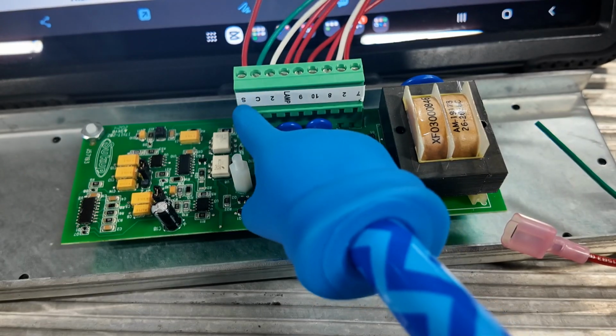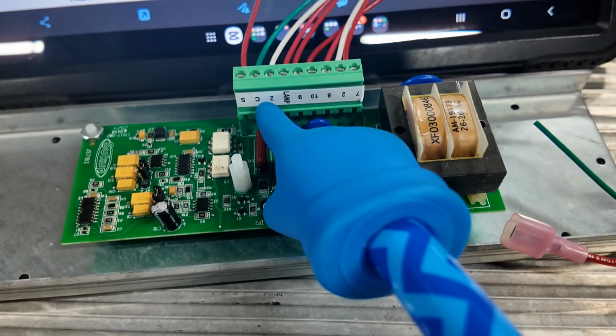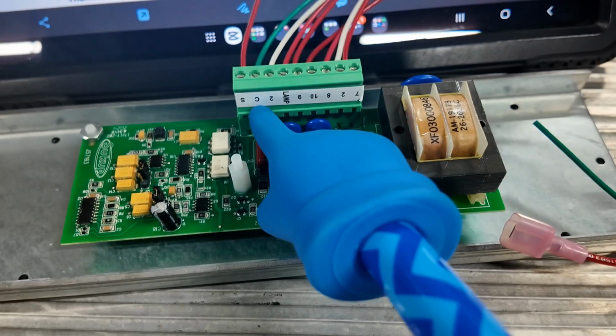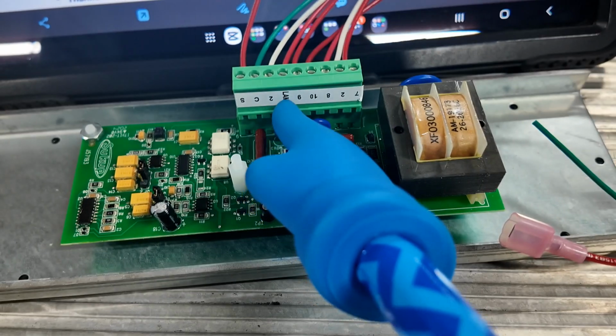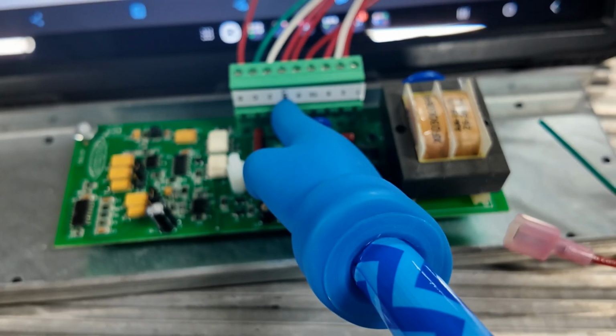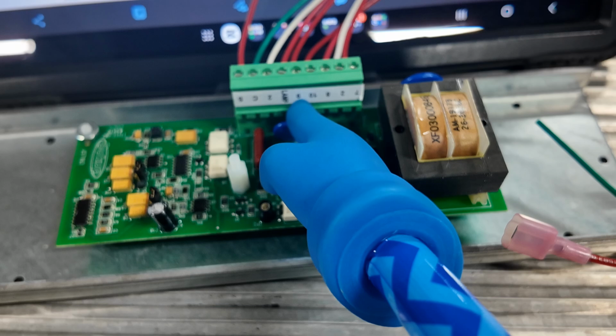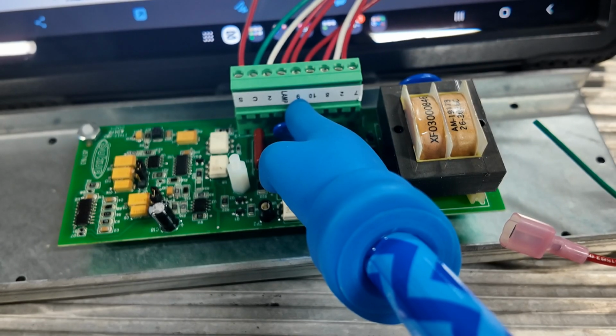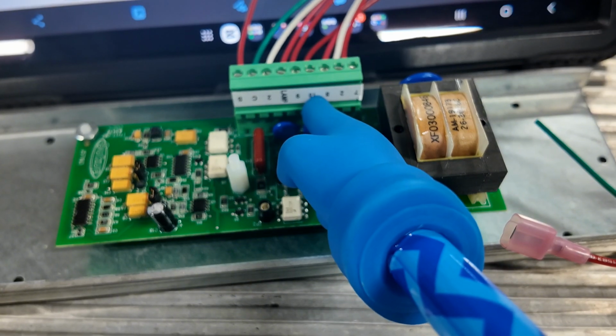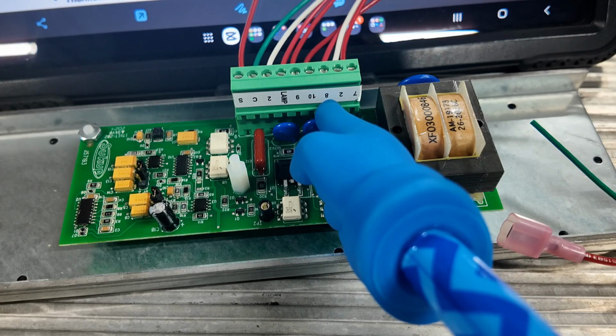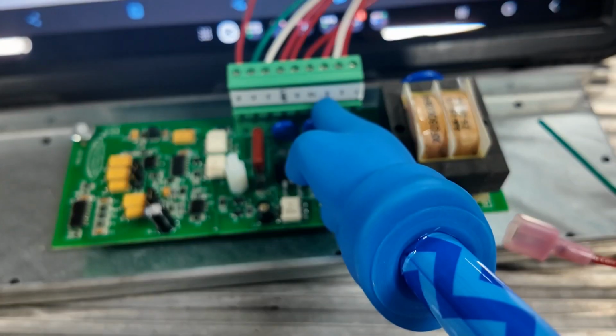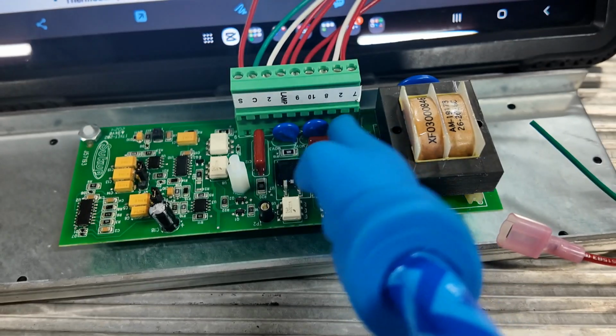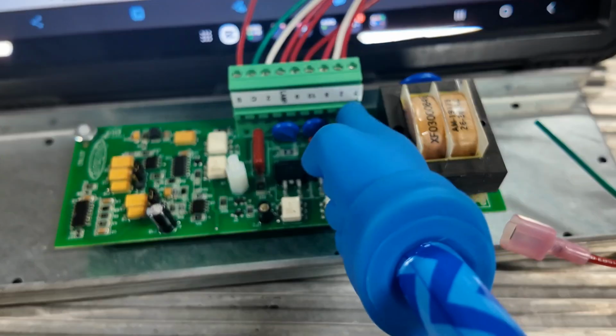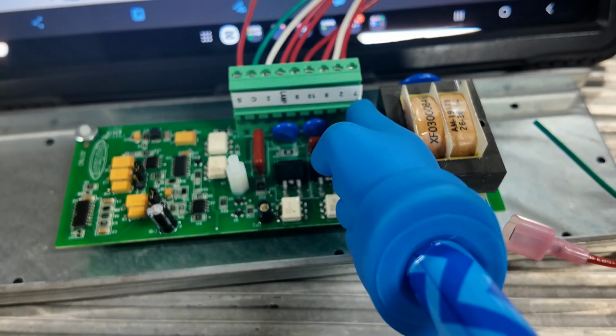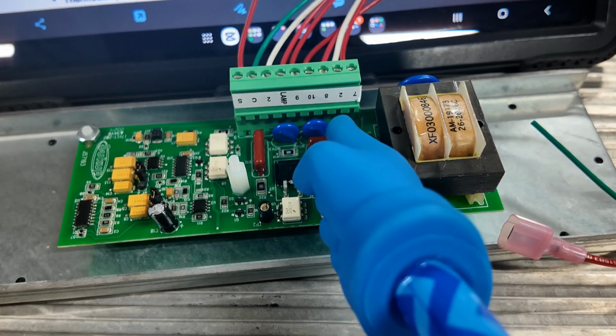In here, we have the S terminal, which is your flame sensor, your C terminal, which is your burner ground, housing ground, your 2, which is neutral, lamp goes to the neutral side of the lamp, the other side of your lamp would connect to 7, 9, which is your ignition transformer, 10, which is your gas valves, 8 is from your thermostat. It would be 110 voltage from the thermostat. The thermostat would turn 8 on and off if you have a thermostat or a humidistat. 2 is neutral, and then 7 is your main power. When you turn your burner on, that starts your purge time and burner ready to run.